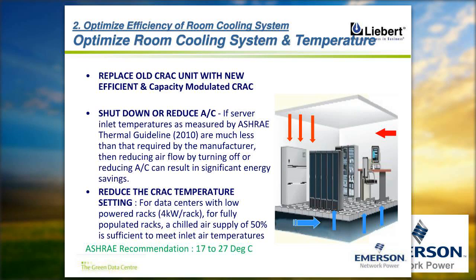Then my next slide: optimize room cooling system and temperature. There are many improved guidelines available from ASHRAE. There was a time in India when we used to maintain 15 or 14 degrees in the cold aisle. That has been upgraded by ASHRAE, and now ASHRAE recommends 22 plus minus 1 for critical applications, or 18 to 27 depending upon your application. Every temperature rise of 1 degree will help you reduce your electrical consumption by 2.5 to 3%. So it is expected that you can maintain the cold aisle or server inlet temperature anywhere between 22 to 23 degrees. That will help you reduce your cost.